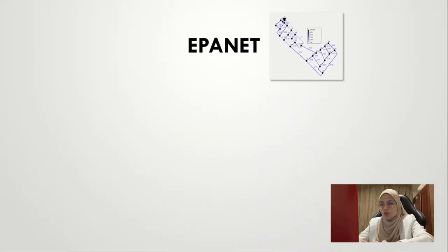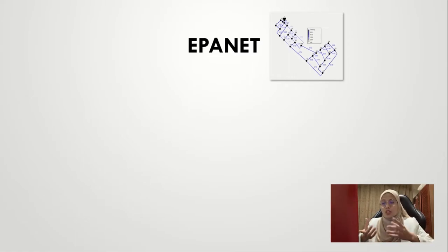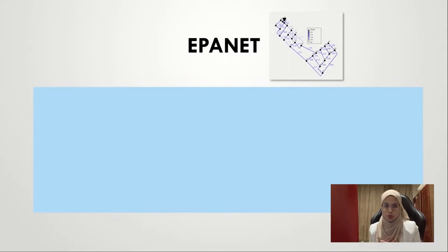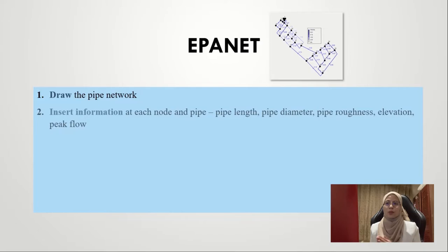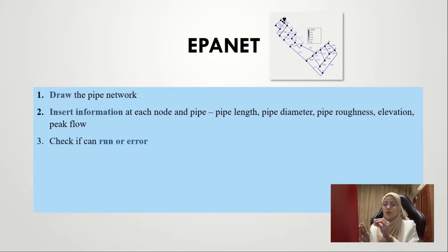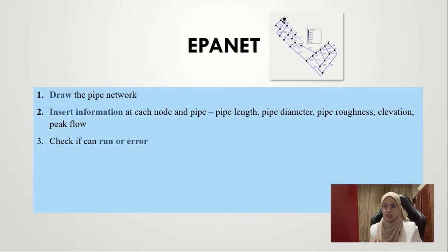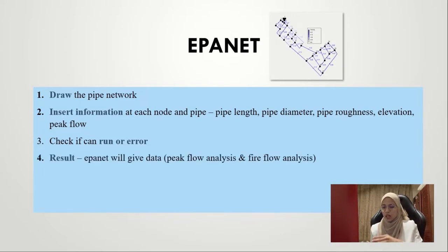In designing this water reticulation system, we also use a software known as ePanet. The first step is to draw the pipe network — we drew it manually rather than transferring from AutoCAD. The second step is to insert information at each node and pipe, such as pipe length, pipe diameter, pipe roughness, elevation, and peak flow. Elevation data was obtained from the Earthwork department. The third step is to check if the pipe network drawing can be run without errors. If successful, ePanet produces results for peak flow analysis and fire flow analysis.